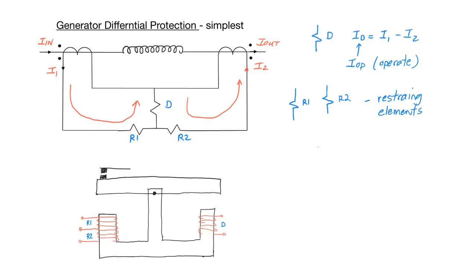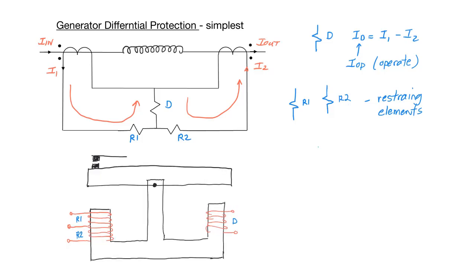On the right-hand side, I've drawn the three elements of the differential relay. All three elements experience a current, but the differential element will experience the current difference between I1 and I2. These are the currents flowing through the two restraining elements R1 and R2. If the difference current is equal to zero, the relay will not operate. We have the differential or operating element and the two restraining elements, tied together at a common point.